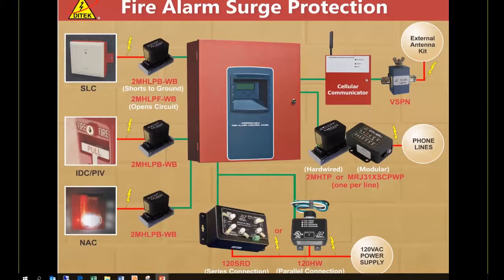Using the 2MHLPB on SLC circuits, I typically would be all right if you're just running between two buildings. But if you're doing multiple buildings, the F is the best one to use because it does open and it's easier to find. If you have multiple buildings with the B series and it shorts to ground, then you have to check all the way along the line to find which module has compromised to replace. On the IDC and the NAC, it's recommended to go with the 2MHLPB series since it runs a little bit hotter current-wise, so that gives you the max continuous operating current of 5 amps.